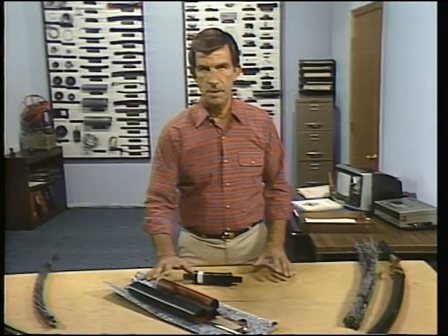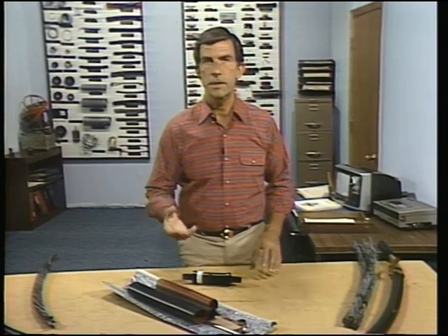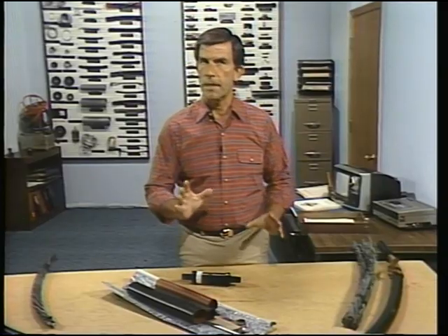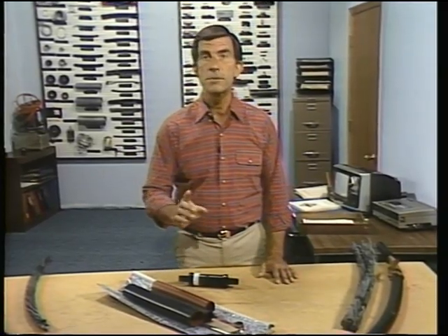With both of these splice kits, a set of detailed instructions will be supplied along with the conductor splice. Now, it's important, as before, that the directions be completely understood and followed to the letter to get the required measurements and to ensure that the splice is installed correctly. Now, when you're using a splice kit, there are several things to keep in mind. First, during the preparation stages, the layers of insulation below the one being removed must not be nicked or damaged.